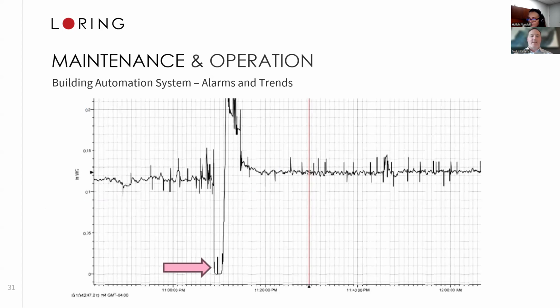Next one. And this is an example of an independent trend that we had set up in a laboratory building, where we had to maintain pressurization in this particular lab, even through a power outage. And what we noticed when we had this data logger set up during a power outage is that that system wasn't functioning properly. So in addition to the energy considerations that you're going to have to be looking at on this equipment, part of what we mentioned earlier with the retro-commissioning is: is the system functioning the way it was designed and intended to function?